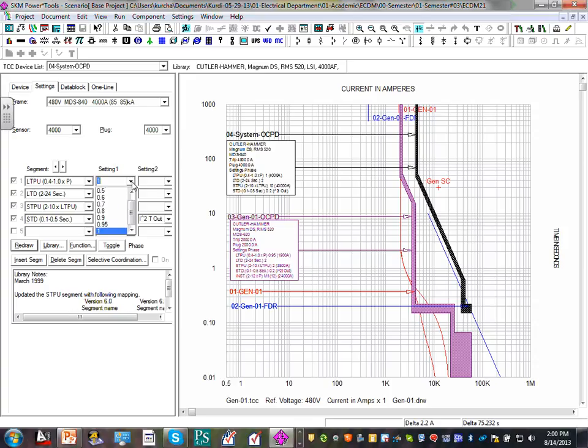When we deal with a breaker at that level, it's always nice to know what the manufacturer options are. Cutler-Hammer, I'm familiar with them, Square D and GE, all of them have adjustable circuit breakers. They have settings that you can adjust, so if you know who the manufacturer is, you can go to SKM and get the exact adjustment for the most part. And with the Power Pack line, you can find a different circuit for that same breaker.